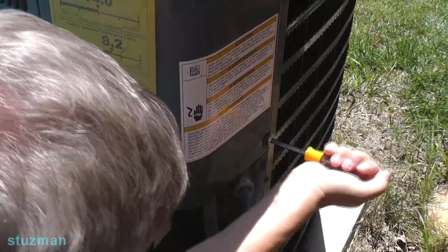Now, even though the unit's not running, as I mentioned earlier, treat it as it's hot until we get a voltmeter in there and actually check to make sure that voltage is off on both legs. This is a 240 volt split phase system.